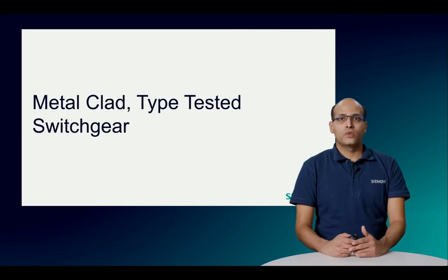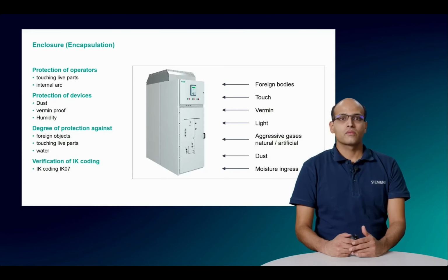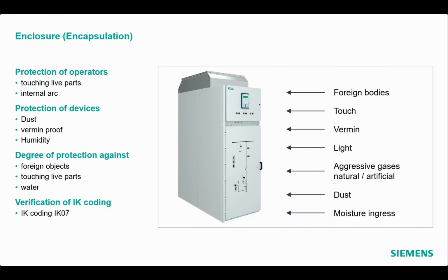Let us now proceed to the next chapter, which is metal-clad type-tested switchgear. Let us first examine the specifics of the switchgear enclosure, also known as encapsulation. The enclosure of the switchgear provides protection for the operators against touching live parts as well as in case of internal faults in switchgear as stated previously. Furthermore, it protects the devices against dust and humidity as well as prevents vermin such as rodents or small animals from entering or damaging the switchgear.